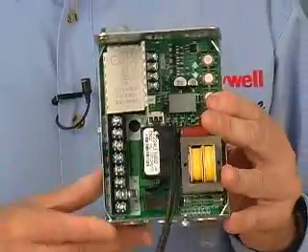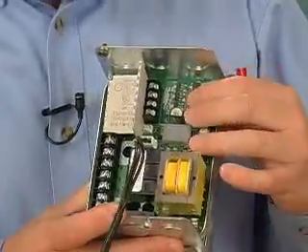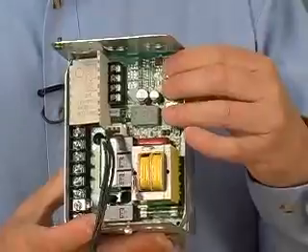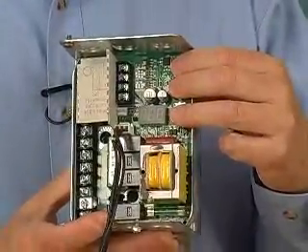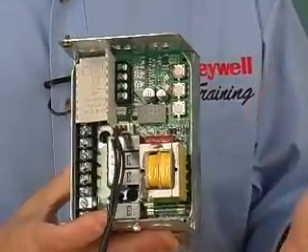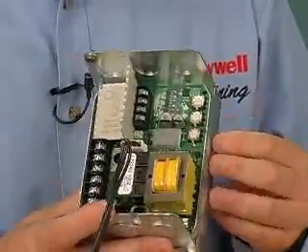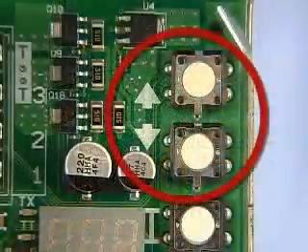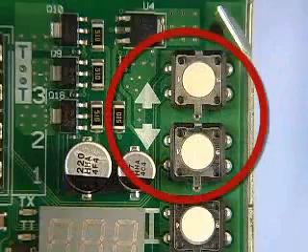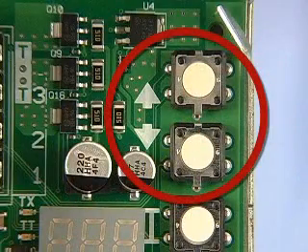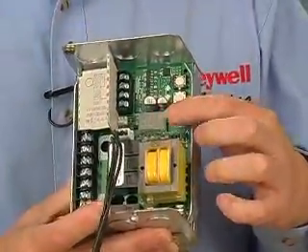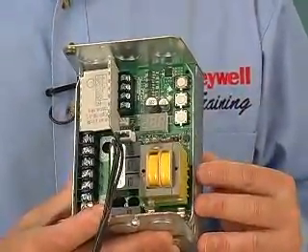Let me show you some of its features. These push buttons are how we adjust the settings. First, pushing all 3 buttons simultaneously for 3 seconds gets us into the setting mode. Then, the up and down buttons change the values of the settings we've selected with the I button, high or low limits, and the differential settings for each. This display shows what we're doing and also reads out operating status.